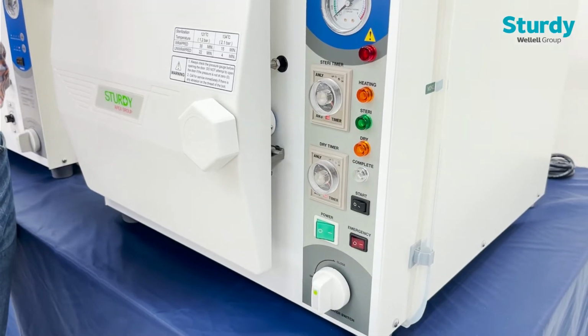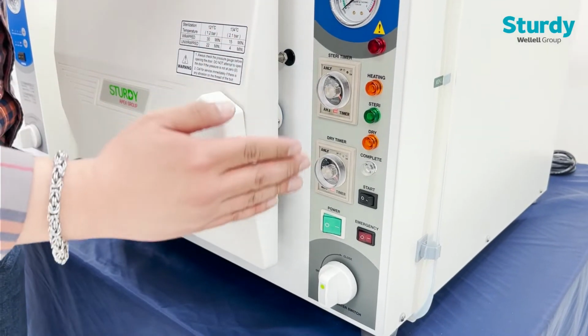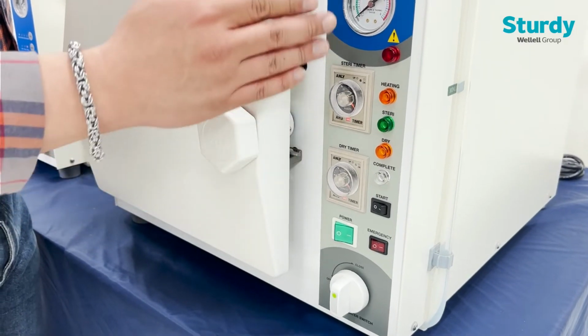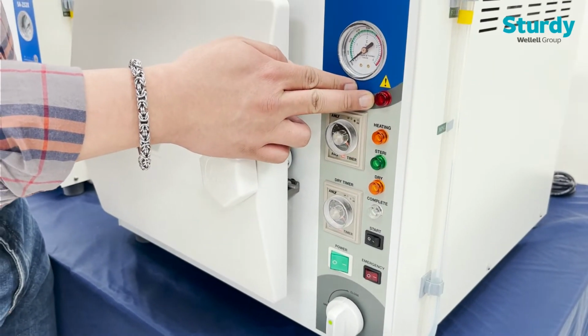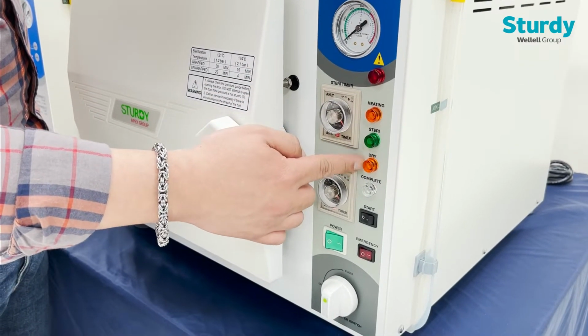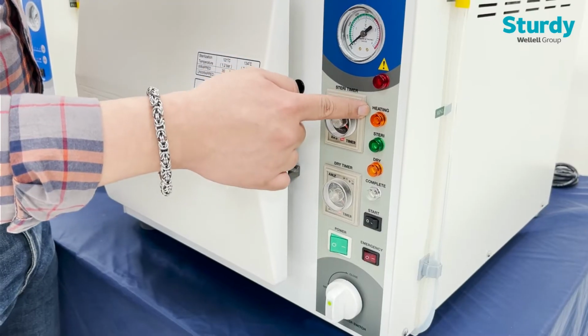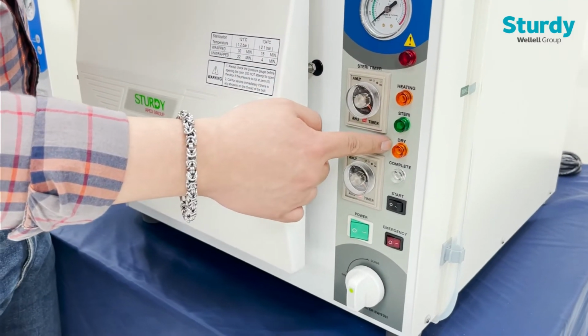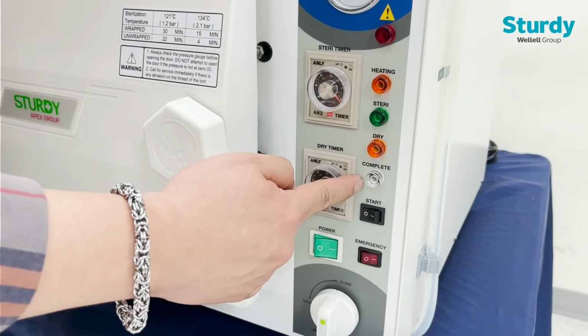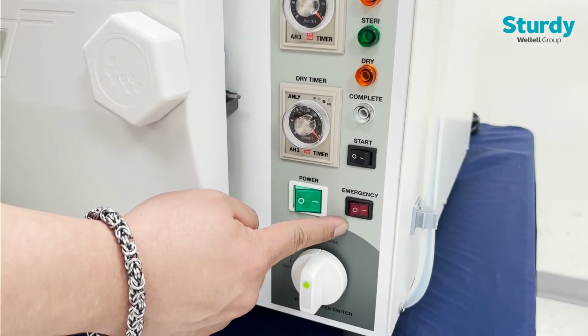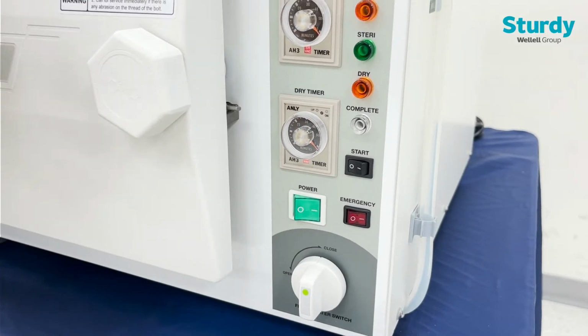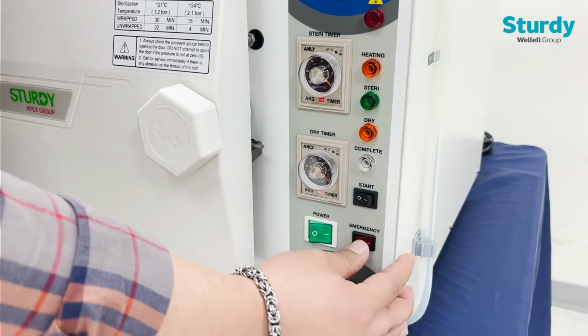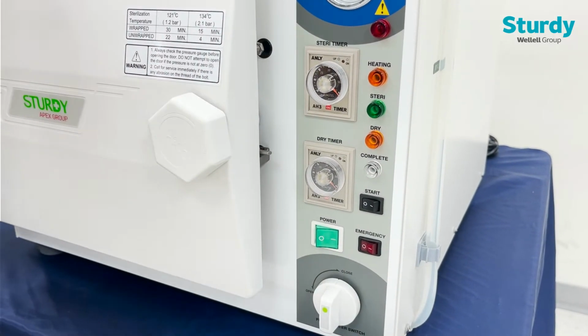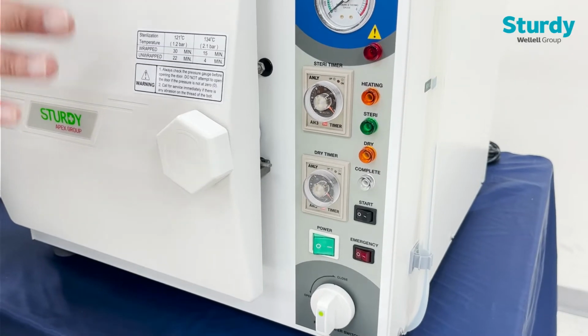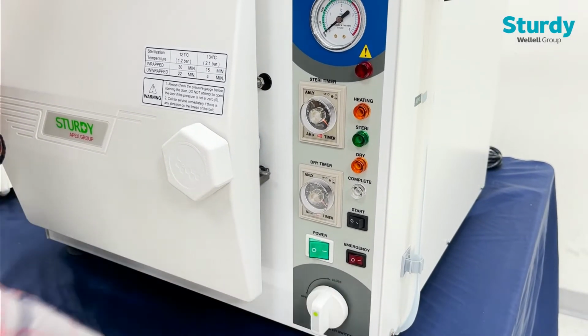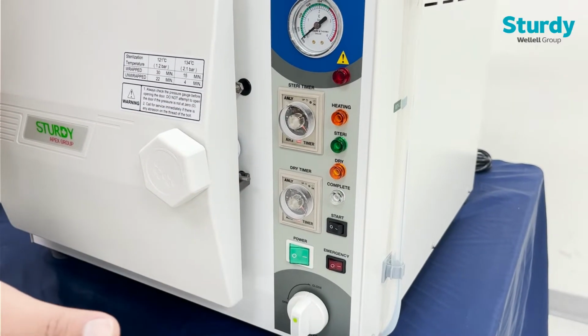The sterilization process begins. Now looking at the control panel, we have various lights indicating either an error has appeared or the stage the sterilization is at: either it's heating up, sterilizing, in the dry stage, or has reached completion. At the bottom we have an emergency button. In case of any emergency during the process of sterilization, this can be pressed, and the sterilization immediately comes to a stop. To restart the process, simply switch off the emergency button and it will continue.